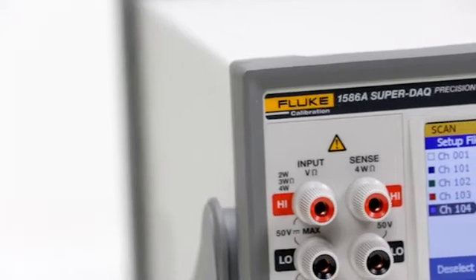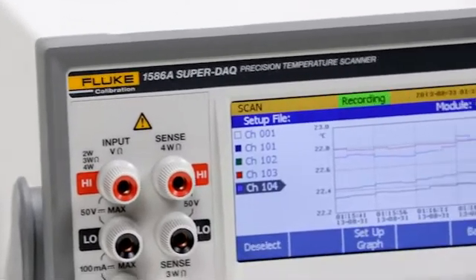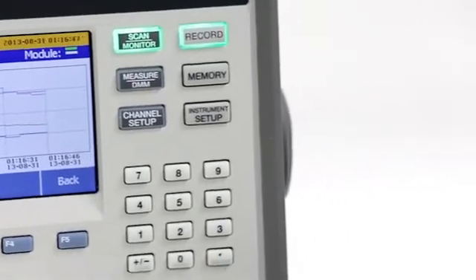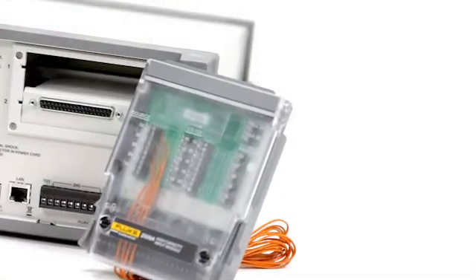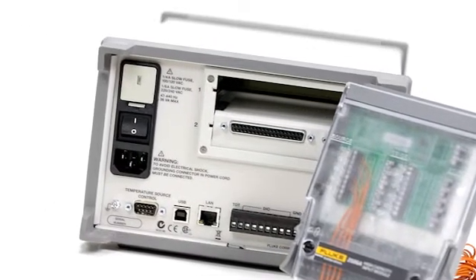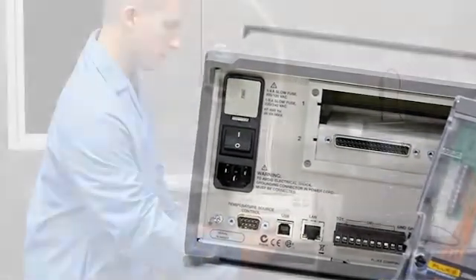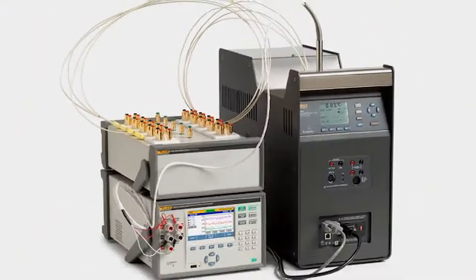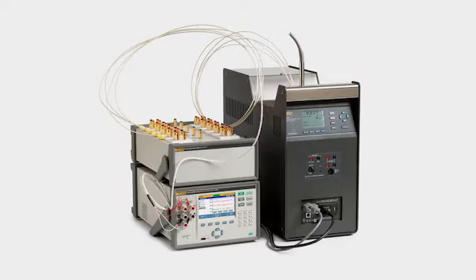The 1586A Super-DAQ is the most accurate and flexible temperature data acquisition system on the market. It scans and records temperature, DC voltage, DC current, and resistance for up to 40 input channels at scan speeds as fast as 10 channels per second. The Super-DAQ can be configured for use as a multi-channel data logger in the factory or as a precision reference thermometer for benchtop sensor calibration in the lab.